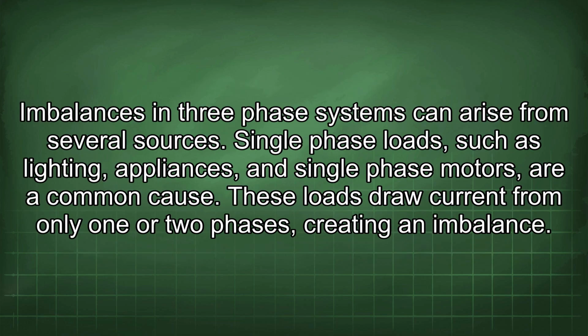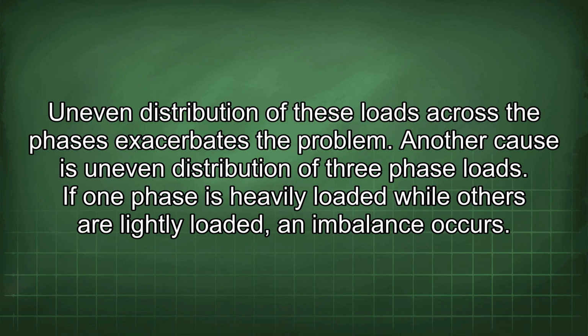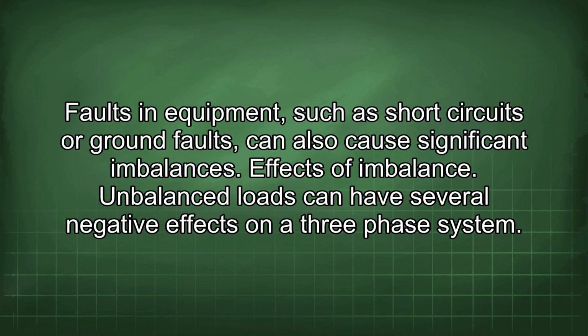Causes of imbalance. Imbalances in three-phase systems can arise from several sources. Single-phase loads such as lighting, appliances, and single-phase motors are a common cause. These loads draw current from only one or two phases, creating an imbalance. Uneven distribution of these loads across the phases exacerbates the problem. Another cause is uneven distribution of three-phase loads. If one phase is heavily loaded while others are lightly loaded, an imbalance occurs. Faults in equipment, such as short circuits or ground faults, can also cause significant imbalances.